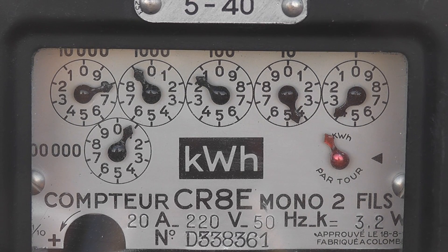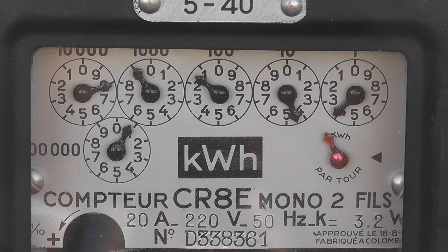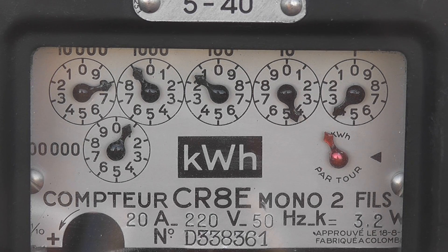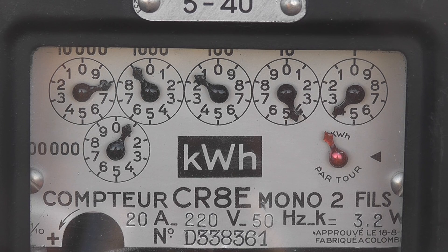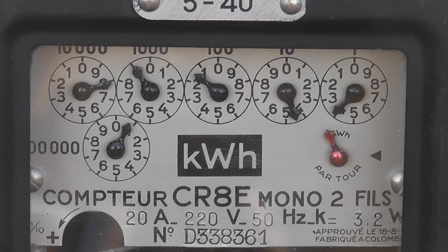This is just a quick video for now, but the meter is still sealed. It has a true reading of 07914 — I'll make it four kilowatt hours. Compteur CR8E, mono 2 fils, 20 ampere, 220 volts, 50 hertz. Constant K is 3.2 watt hours per revolution. Range: 5 to 40 ampere.